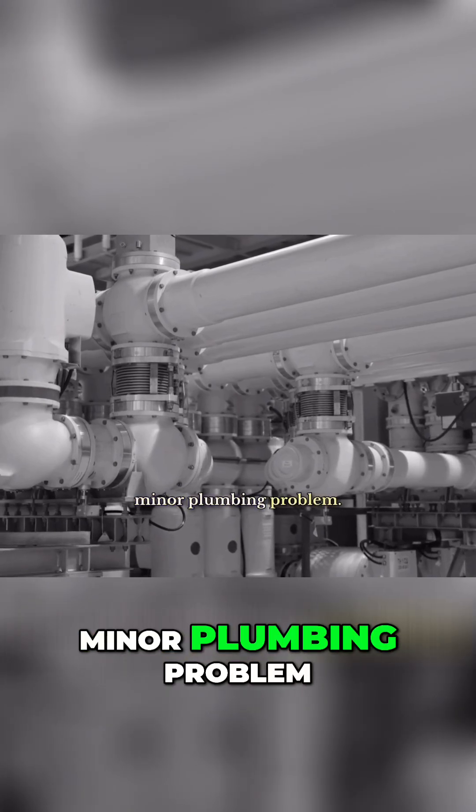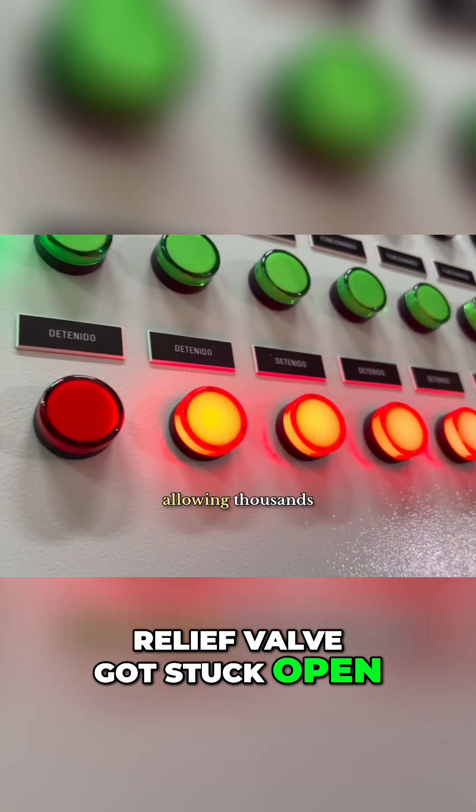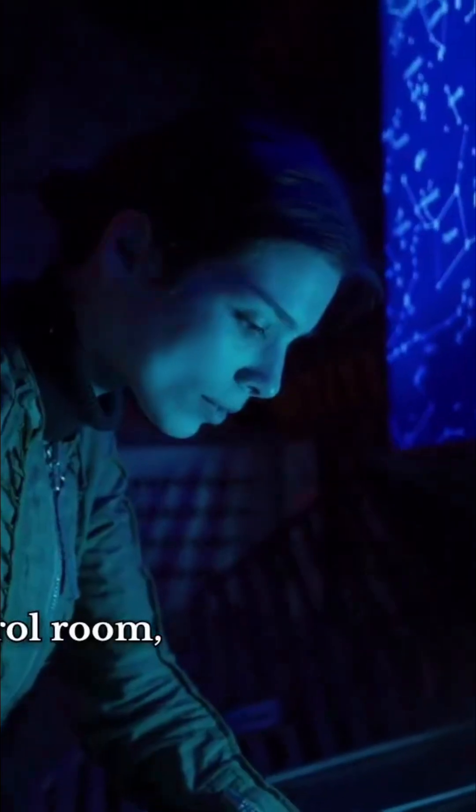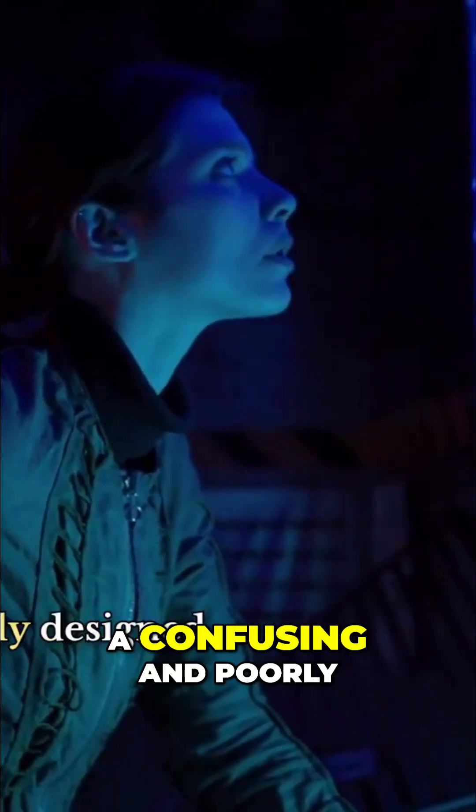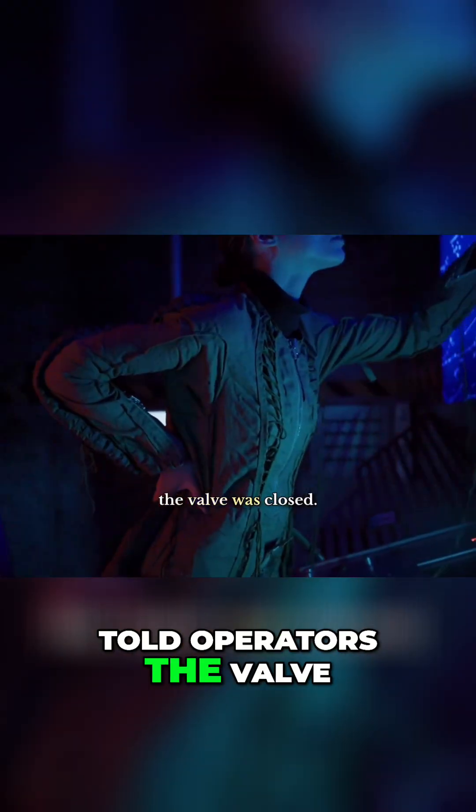It began with a minor plumbing problem, but then a crucial relief valve got stuck open, allowing thousands of gallons of reactor coolant to drain away. In the control room, a confusing and poorly designed indicator light falsely told operators the valve was closed.